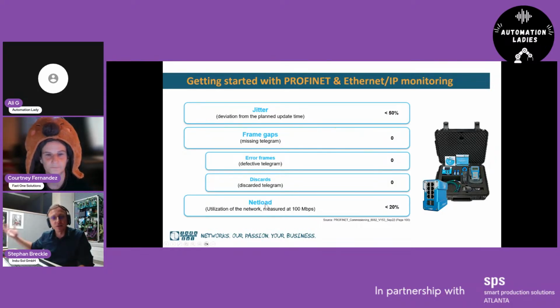Net load is the amount of packages you transmit over your system. If your bandwidth is 100 megabits per second, you have to make sure you stay below 20% utilization inside your network. People coming from the IT world often see something like 80% as normal, it depends on whether you look at milliseconds or seconds. But because of the cyclical communication, we have a maximum of 20%.